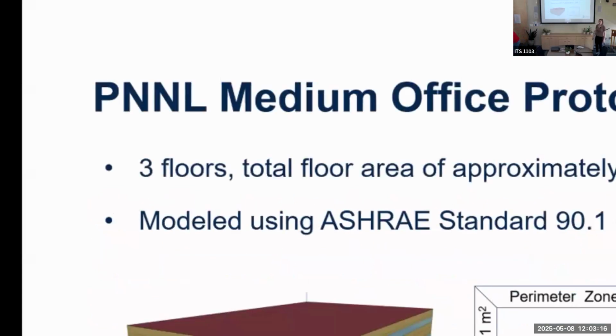To do this, we used EnergyPlus models, and our model was a PNNL medium office prototype building. PNNL has a lot of different prototype building models for commercial and residential buildings. We used the medium office one. It has 3 floors with a total floor area of around 5,000 square meters, or 54,000 square feet, and it uses ASHRAE 90.1 in the 2019 version. It's got 5 zones on each floor, so there's a core zone and 4 perimeter zones. And that's just a picture of what it looks like.